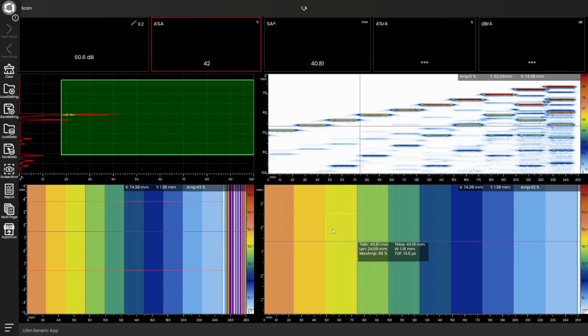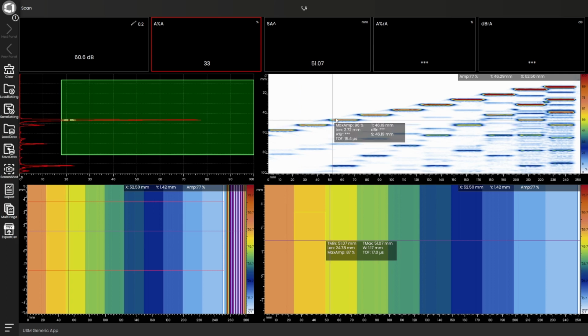So the length is going to be the length along the scan axis. Width isn't as useful here because we only acquired one stripe of data. So our vertical distances aren't all that meaningful on this type of line scan, but the length of that box is a good indication of the actual distance along the scan axis. So my box, as I drew it there, is right about an inch, 24 millimeters and change. I can draw those same boxes on the B-scan, getting to where the echo for that really begins to drop off, so sort of center of the transducer. So there, again, showing about 25 millimeters of length.